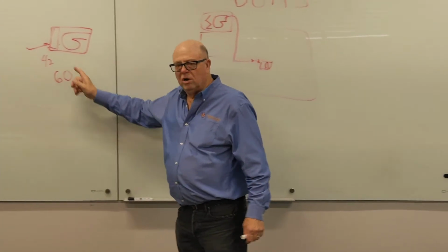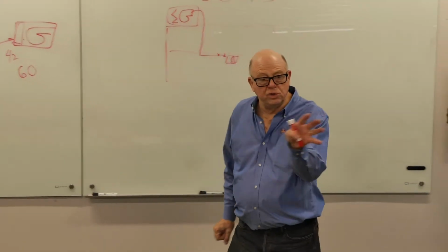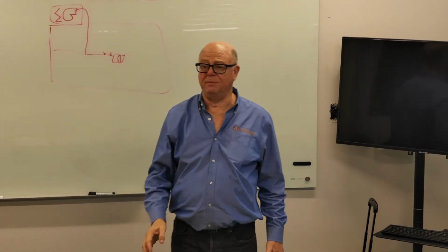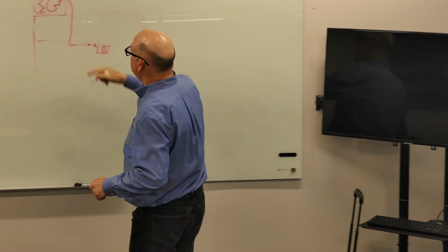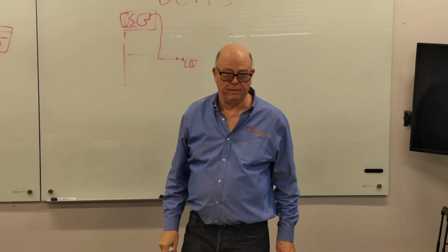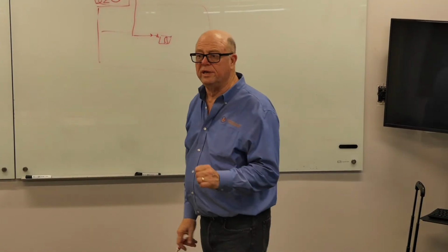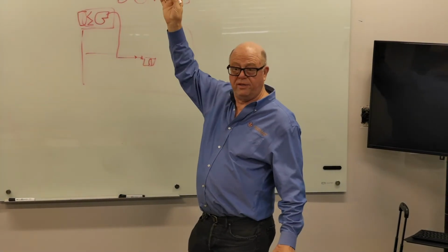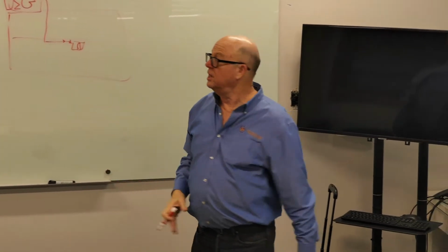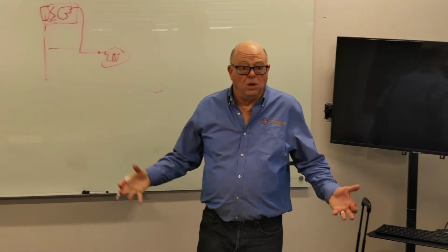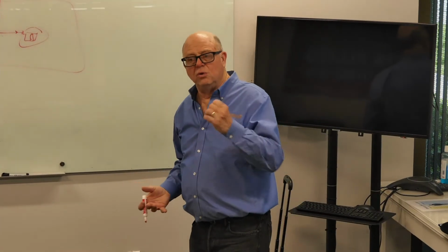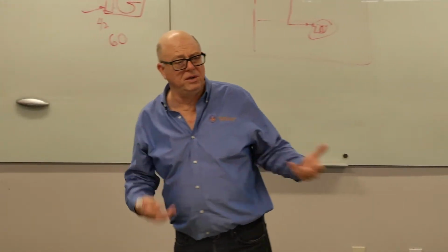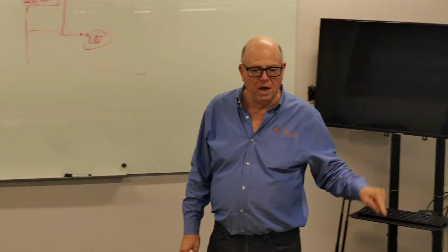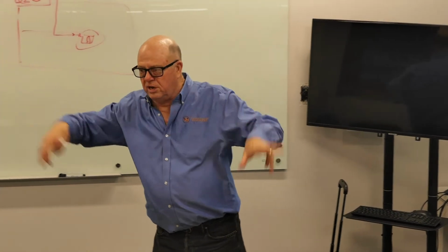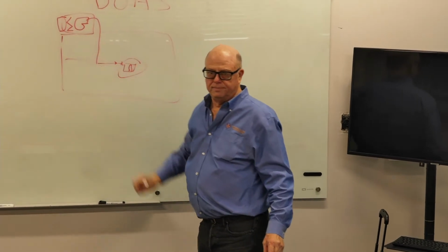So VRF doesn't work the same. What should have happened, and this gets us back to DOAS, and anytime you do VRF, is this needs to have cooling. The reason it needs cooling is so that you can knock some of the moisture out of the air before it goes down to the fan coils, because if it's a VRF fan coil down here, at low load it won't dehumidify. Now in normal office applications, it doesn't matter. Classrooms, it doesn't matter. It's not a big deal. But anything that's going to be occupied at low load, at night, take your pick, you need cooling up here.